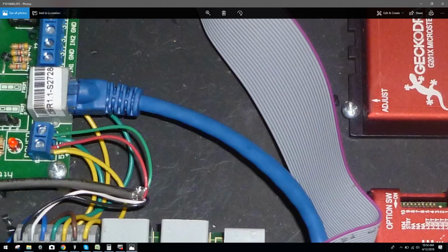You should never, ever, ever be having multiple leads going into one terminal block. You use a terminal splitter, you wire one lead from the terminal block, and then attach these multiple leads to a terminal block that's used as a splitter. That is the correct process to do. Okay? And when it's done that way, not only does it look neater, your system is done correctly for servicing, and also the performance is bulletproof.